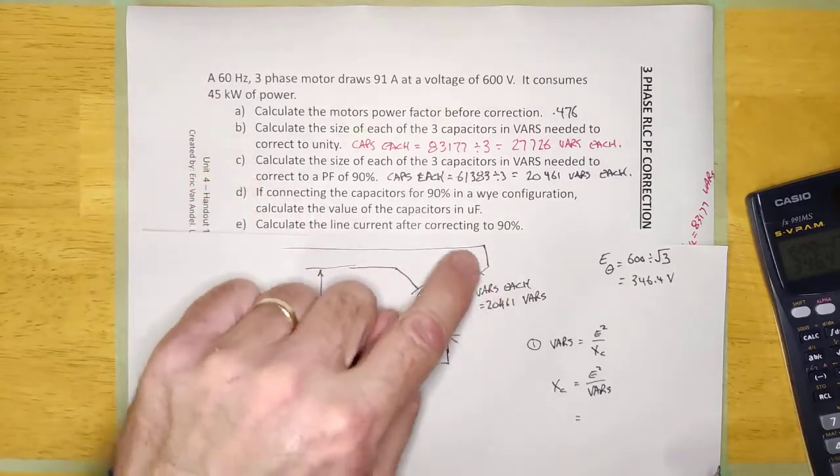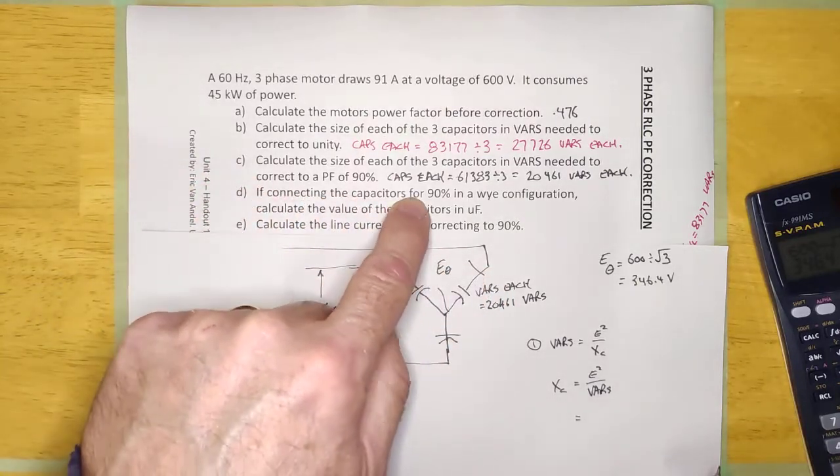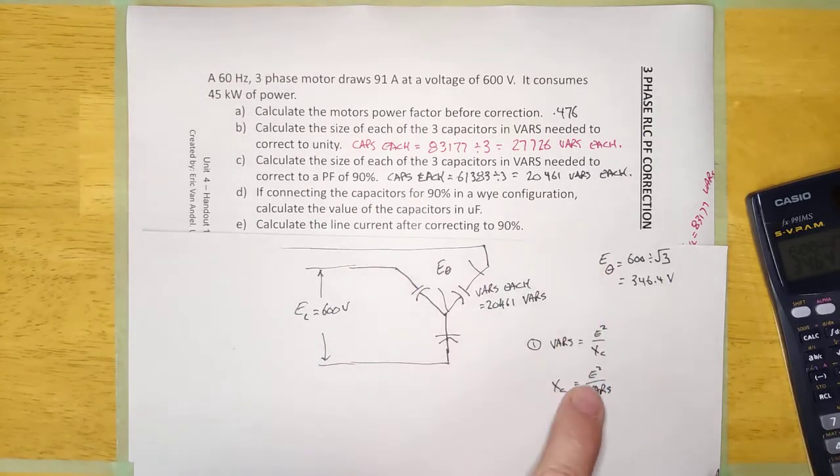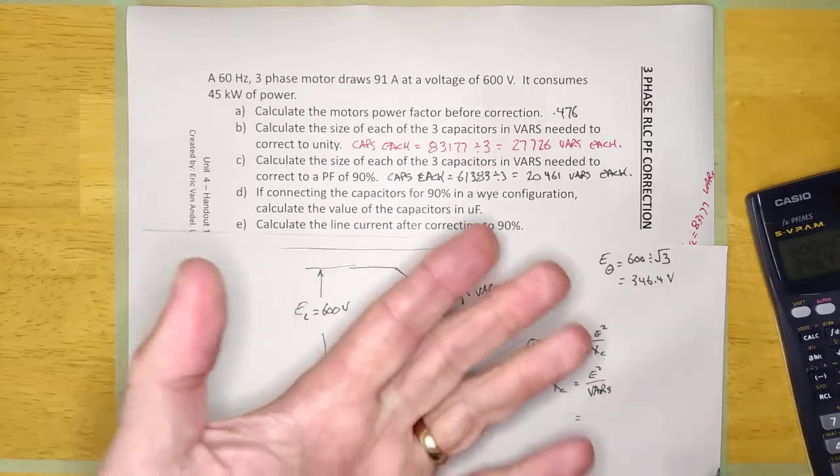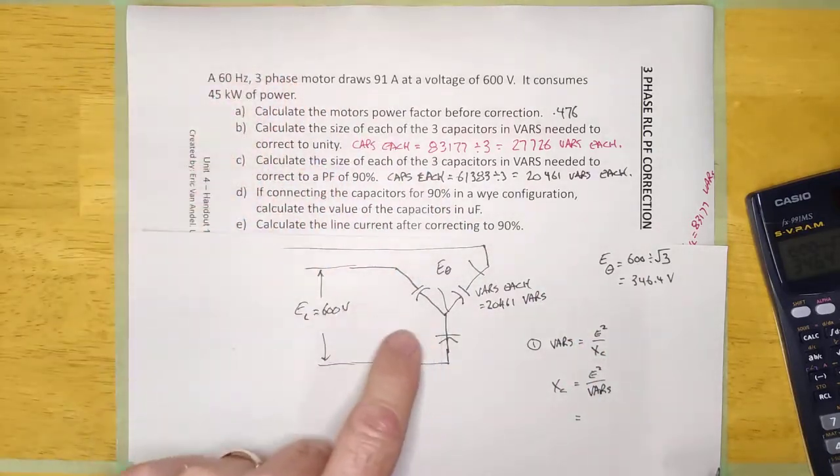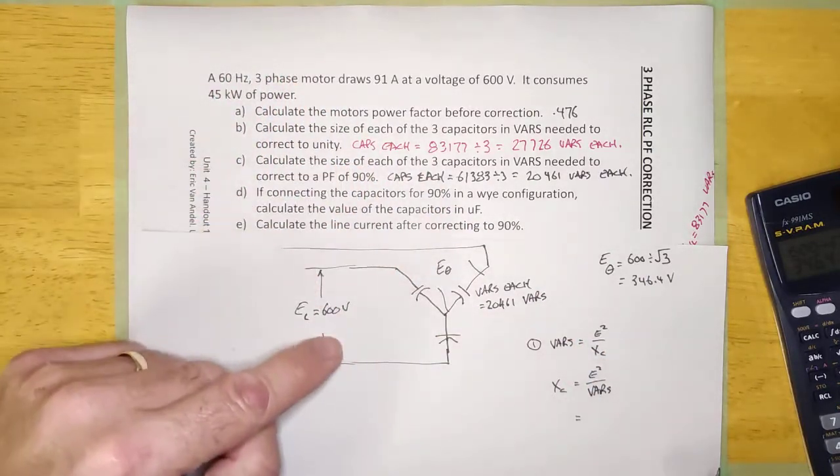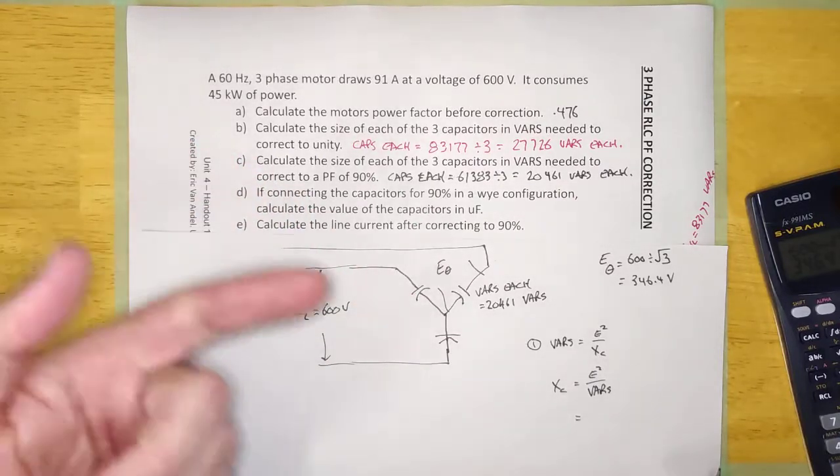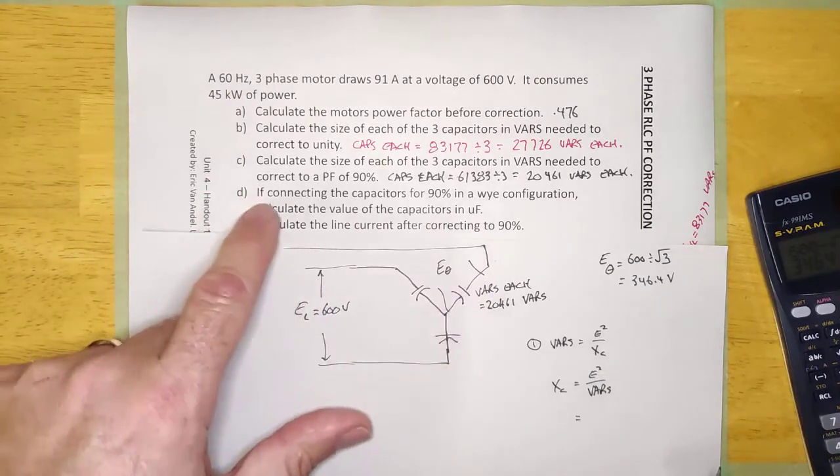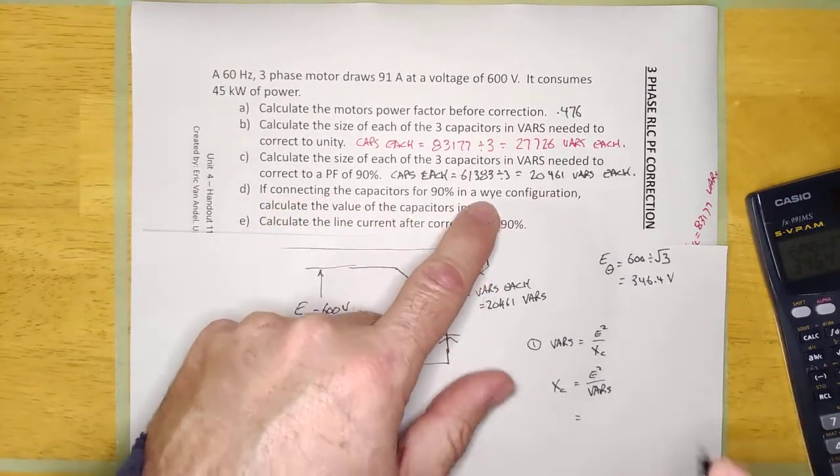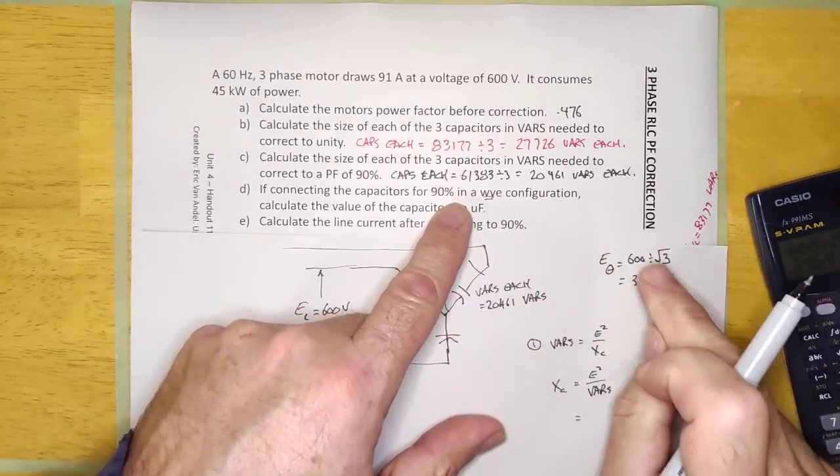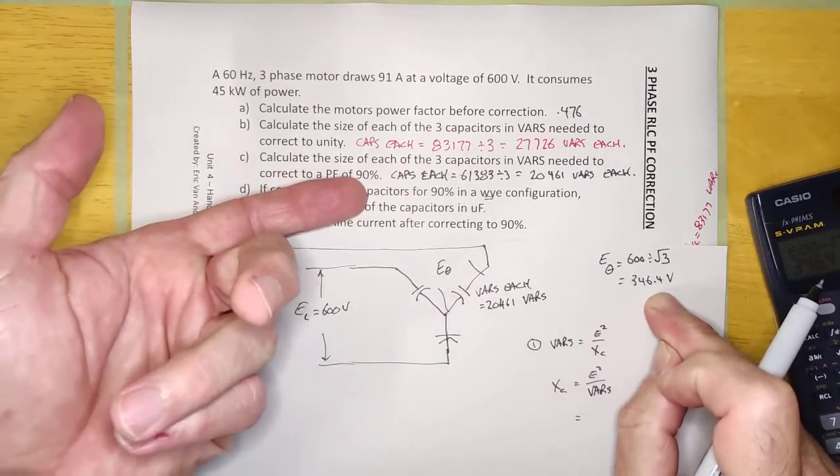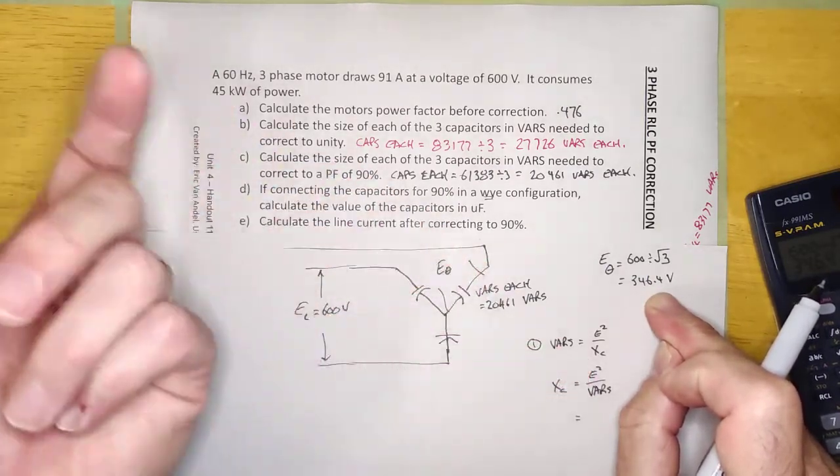Now, if this thing happened to be delta, and it said here, if connecting the capacitors in delta, I would still need to use the phase voltage in this formula. But the phase voltage would be equal to the line voltage. So, it would be less of a big deal because E line is equal to E phase. So, I go, 600 squared over 20461, all right? But it's really important to notice how it's connected. And if it's Y, I have to take the line voltage and divide by root 3 before I apply this formula. If it's delta, I still have to use the phase voltage, but it will be equal to the line voltage.